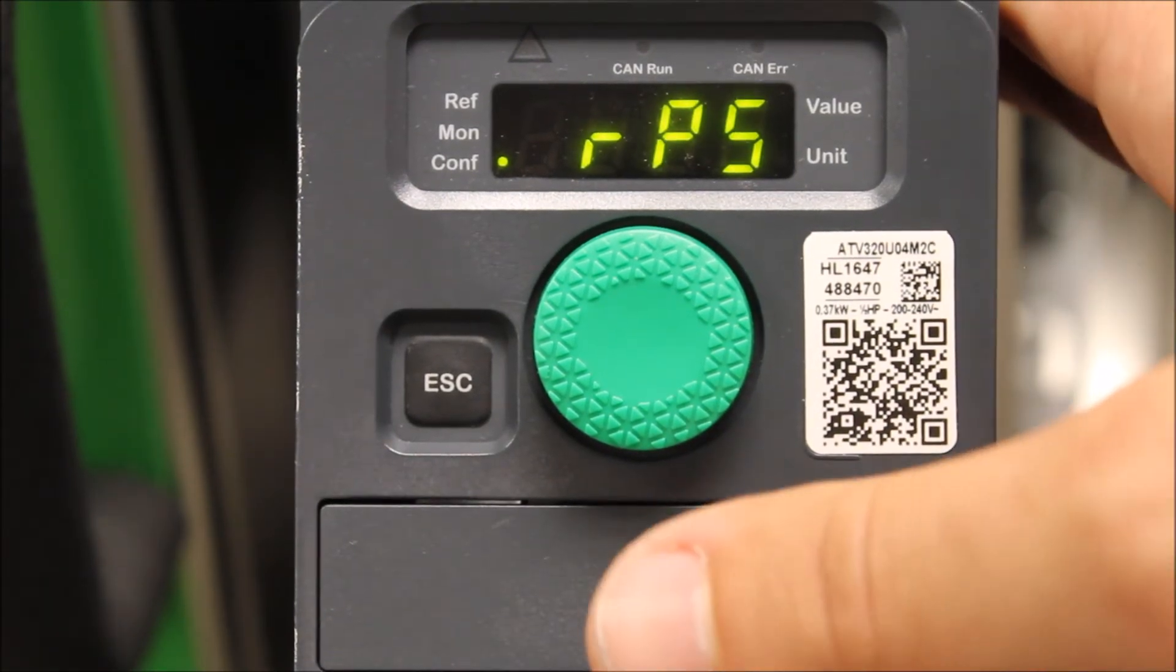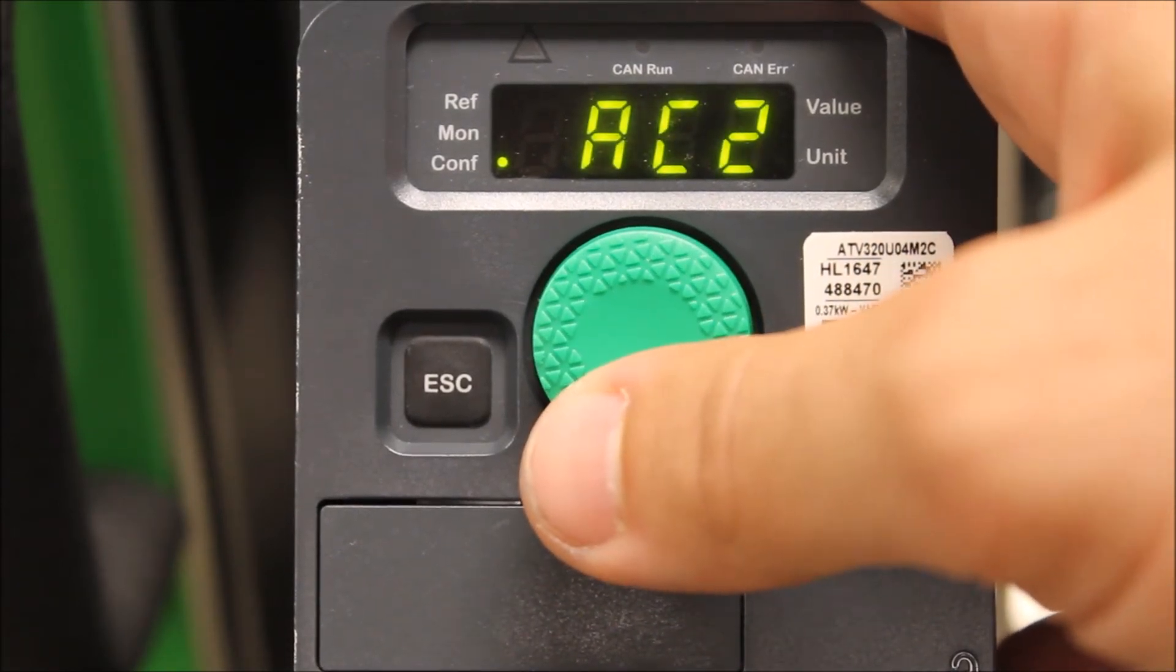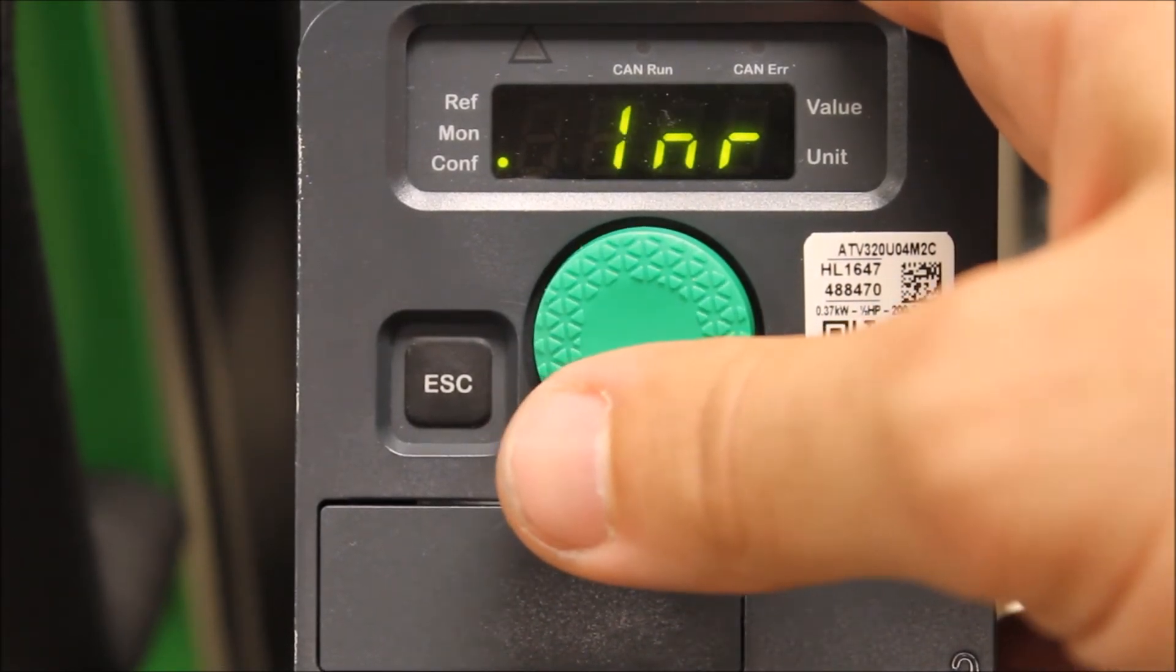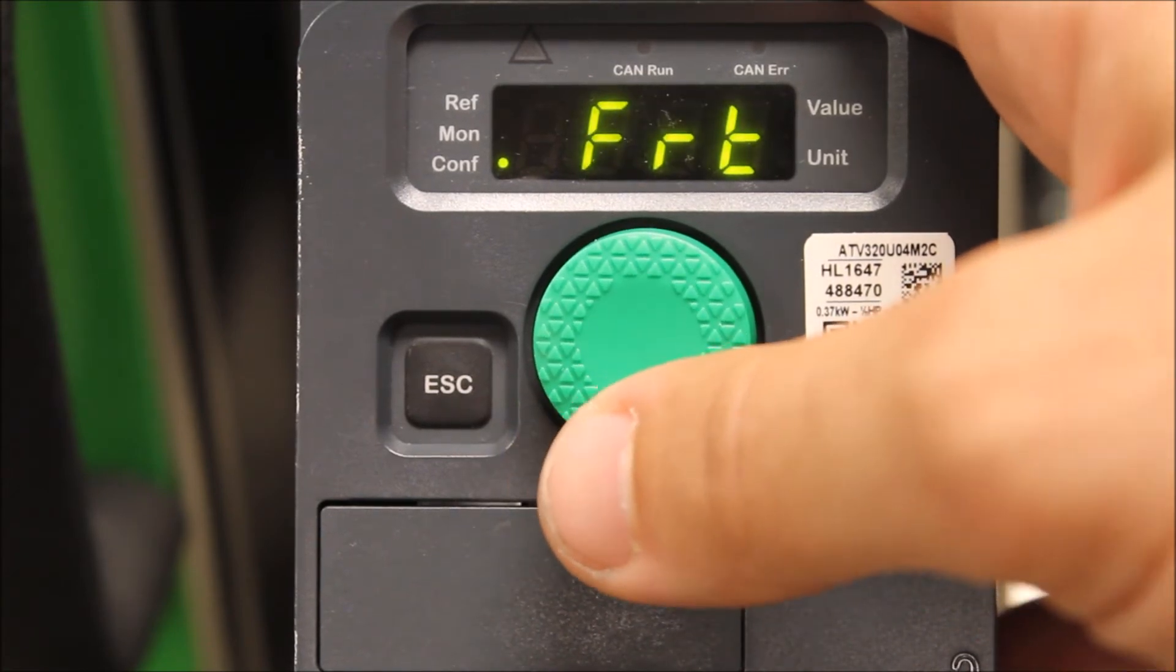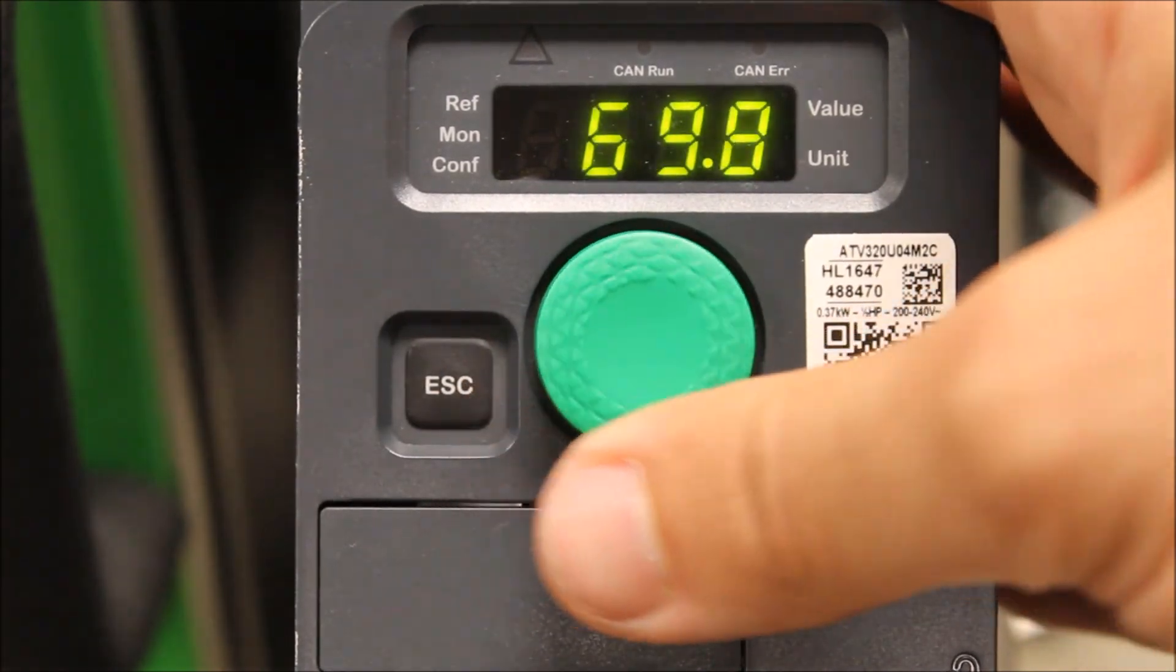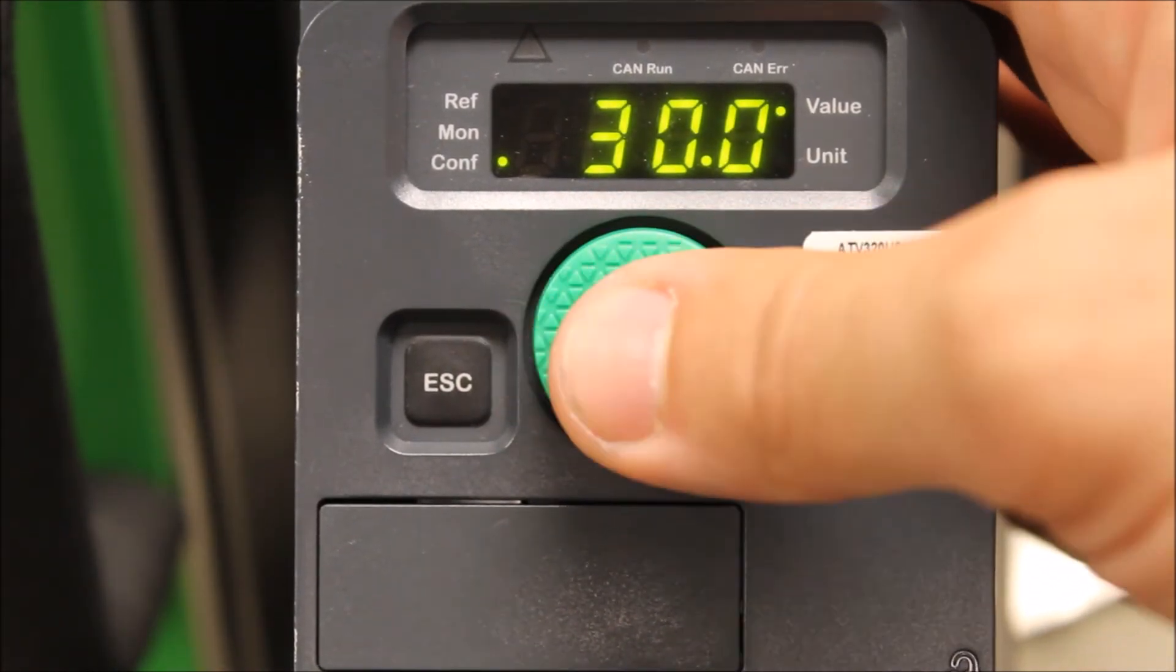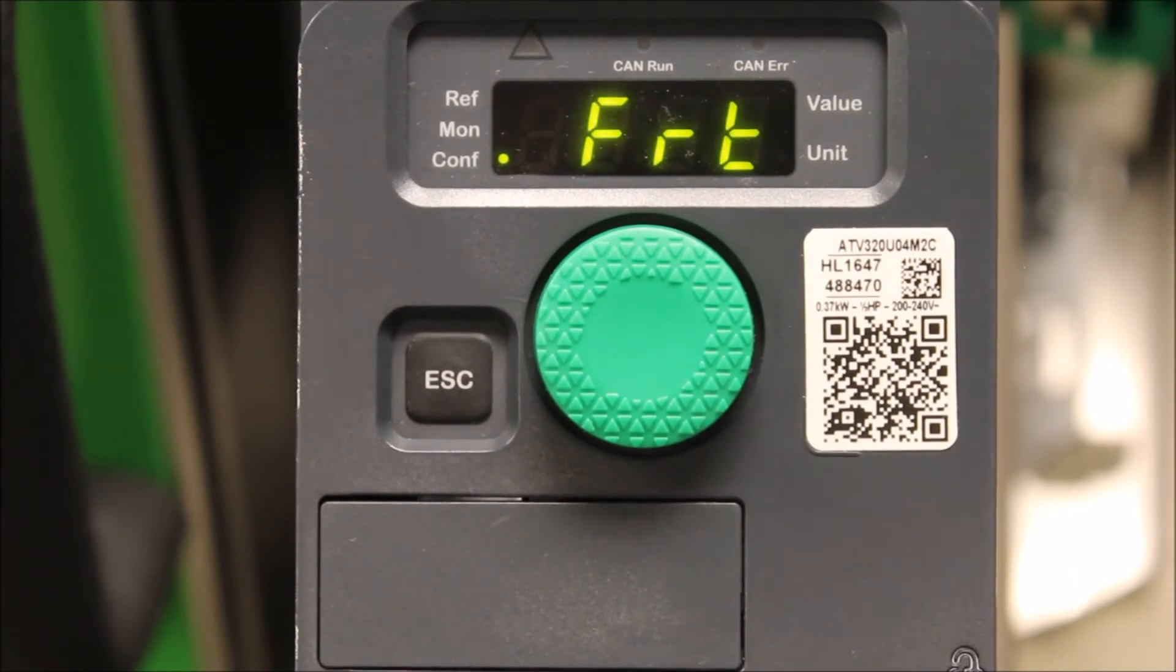I mentioned is using a frequency threshold, and that's parameter FRT. Let's go ahead and find that. This is a frequency threshold, so let's make it 30 Hertz as an example.